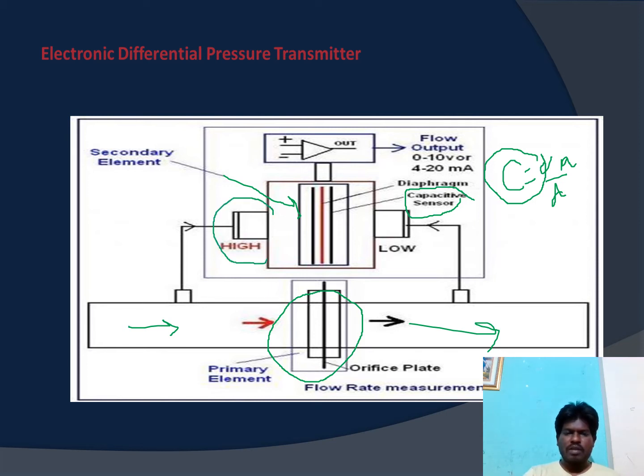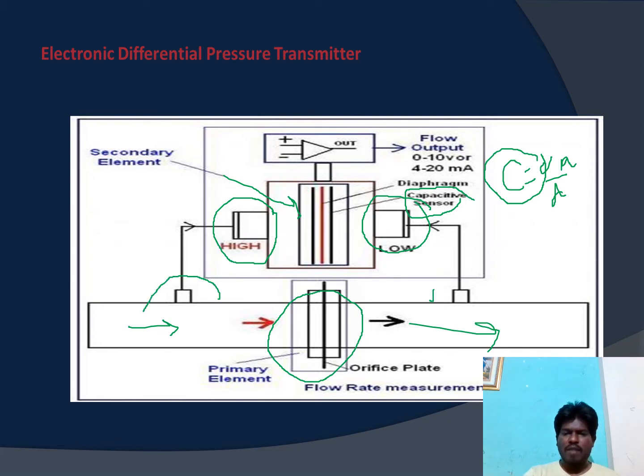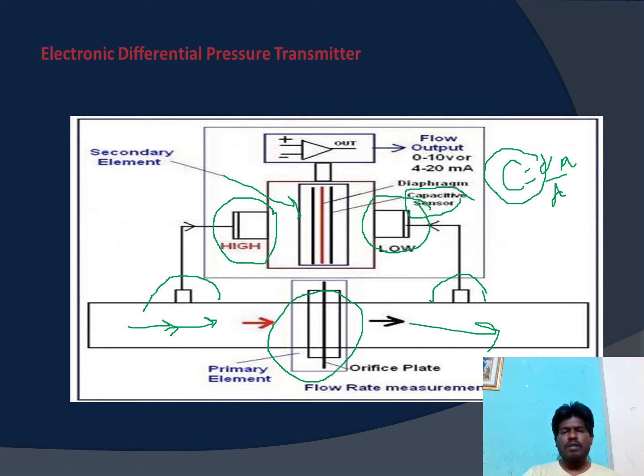This section has two different terminals: a low pressure terminal and a high pressure terminal. On this pipe we can see there is one tap on one side and another tap on the other side. Obviously from one side there will be higher pressure and from the other side lower pressure. This low pressure is applied to one side of the capacitive sensor and the high pressure side is connected from the other terminal.